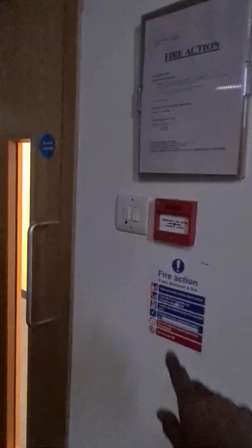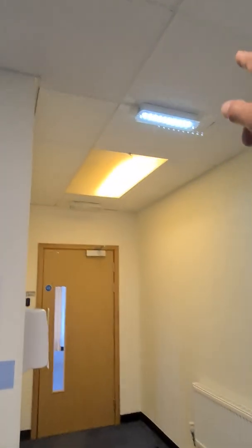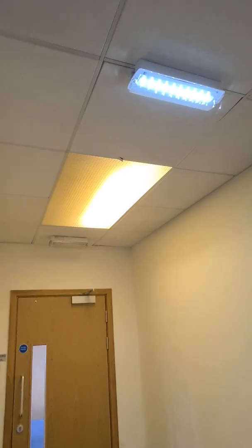Right, as you go up the stairs, your next emergency light test point is here, which is FK4, and that affects 2 emergency lights here, one of which has failed. So you've got 2 emergency lights in this lift lobby landing. Now if you come through here, you find that there's an emergency light test point here which affects this lobby, and that's that emergency light there.